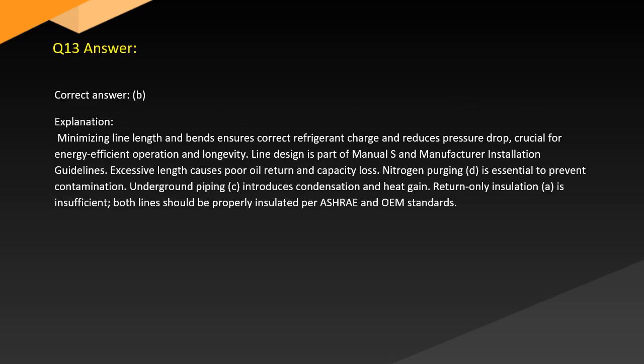Answer. Correct answer: B. Explanation. Minimizing line length and bends ensures correct refrigerant charge and reduces pressure drop, crucial for energy-efficient operation and longevity. Line design is part of Manual S and manufacturer installation guidelines. Excessive length causes poor oil return and capacity loss.